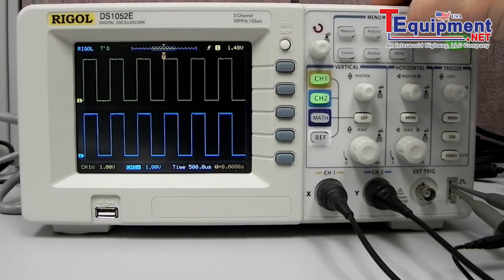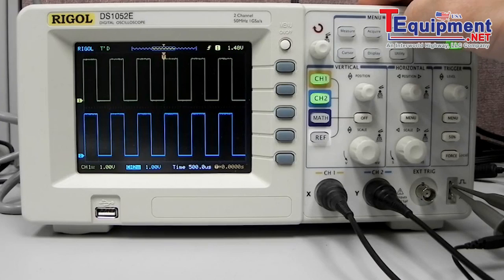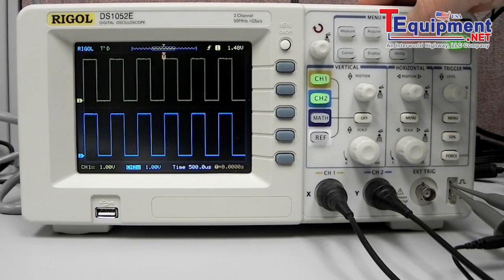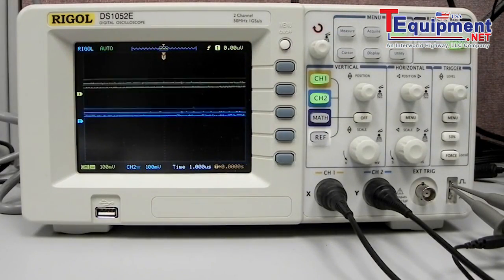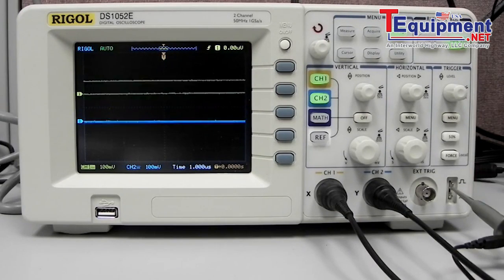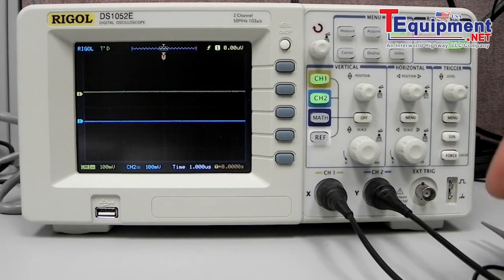If we want to get back to factory default settings that's very straightforward. We just want to press storage, select waveform, and rotate down to factory and then we can load the factory settings. If I disconnect the probes you can see now we're back to DC.